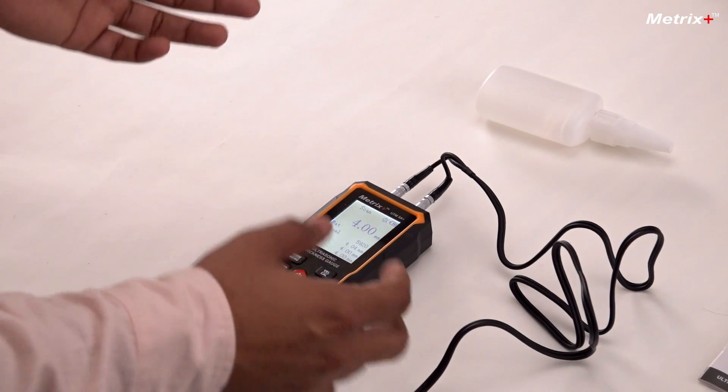So that is how you can calibrate the instrument. If the values are drifting from the actual values, then you can calibrate. It is not necessary to calibrate every time you use it — only when it is out of the tolerance range.